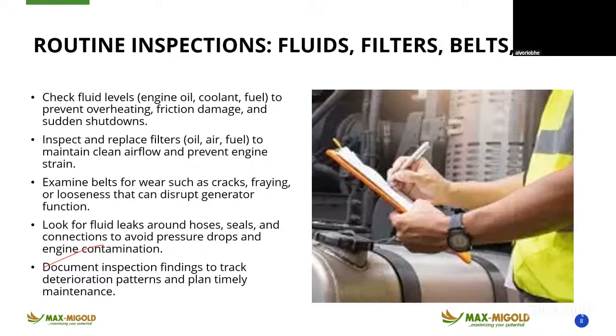If you need to change the air filter, it's just like your nose: if your nose is blocked, you look for an alternative way to breathe. The same way, if there is no fresh air coming to the engine to cool it, the engine will look for an alternative way to cool itself. It might be the gasket; you will see the gasket expanded and misaligned, then oil will start leaking. Before you know it, the generator will break down and you start calling for overhauling. Like I tell people, if you tell me you know how to do overhauling, it's because you didn't pay attention to the right maintenance you were meant to do. If you pay attention to the simple maintenance things, you will not think of doing overhauling.